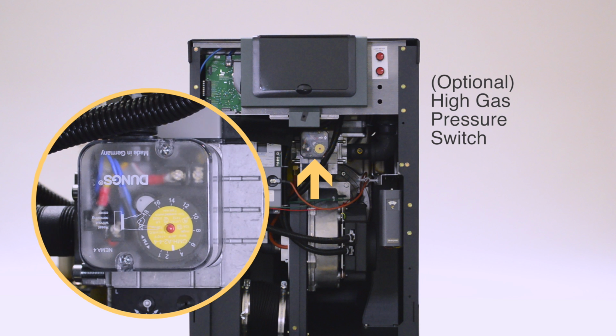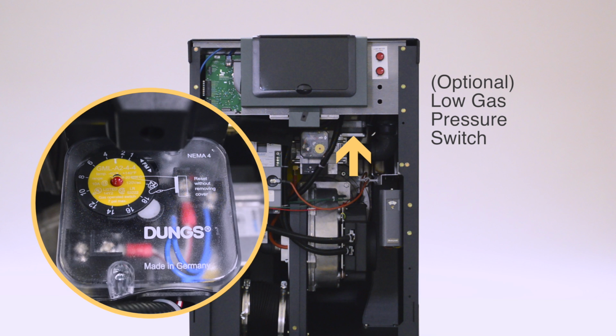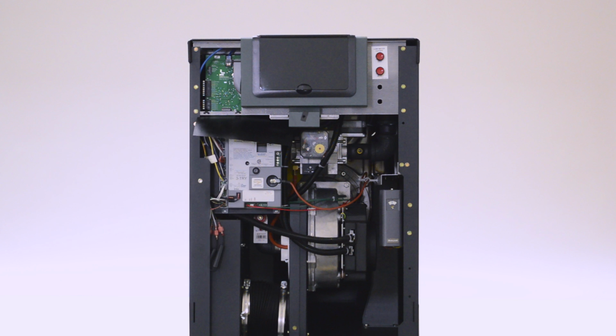Your unit may have an optional high gas pressure switch. If the gas pressure regulator in the valve fails, the high gas pressure switch automatically shuts down the unit. The high gas pressure switch is set at a manifold pressure of 3.0 inches water column for natural or propane gas, or an optional low gas pressure switch. Automatically shuts down the unit if the gas supplied to the unit drops below the factory setting of 3.0 inches water column for natural or propane gas.